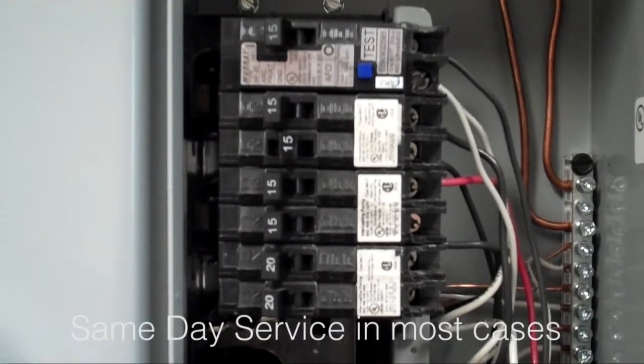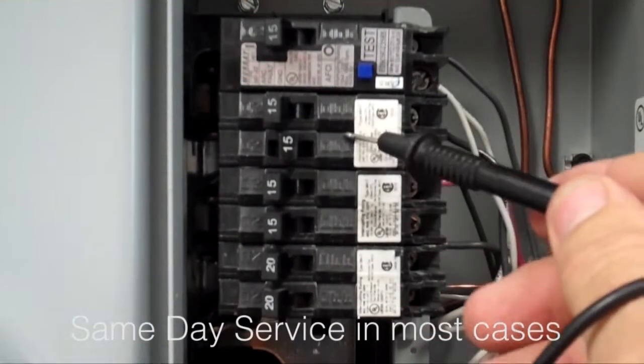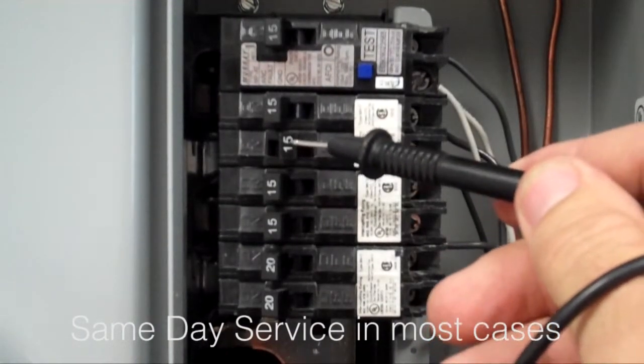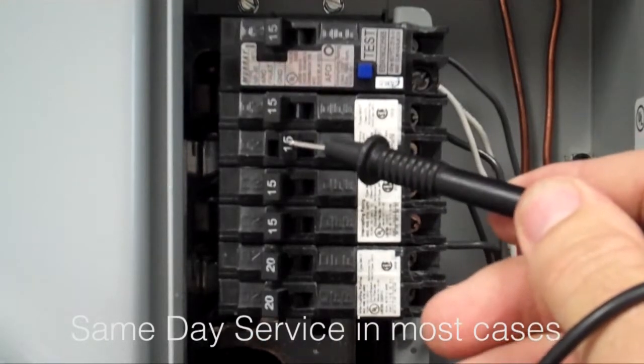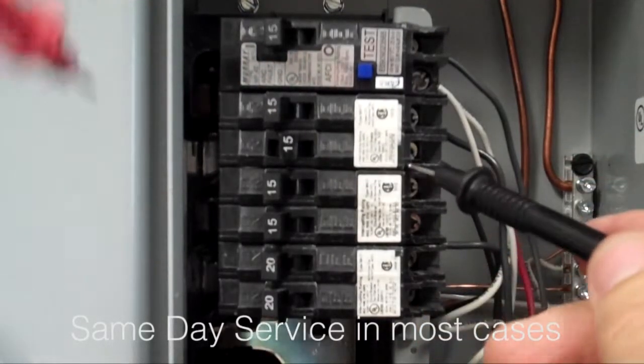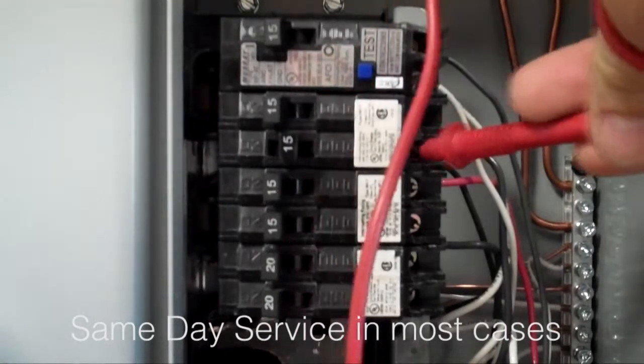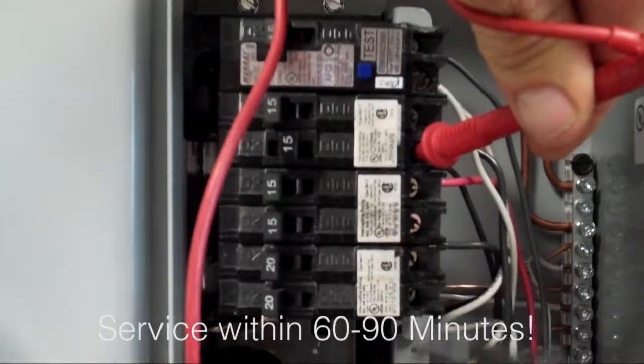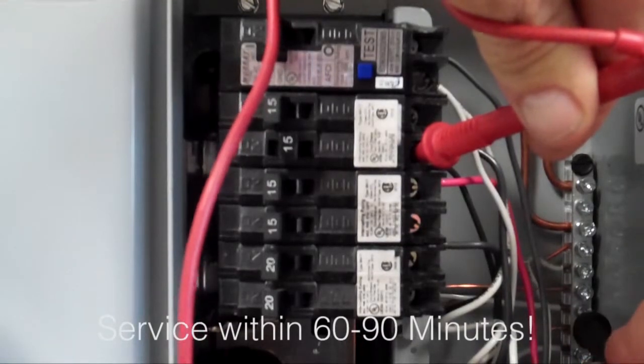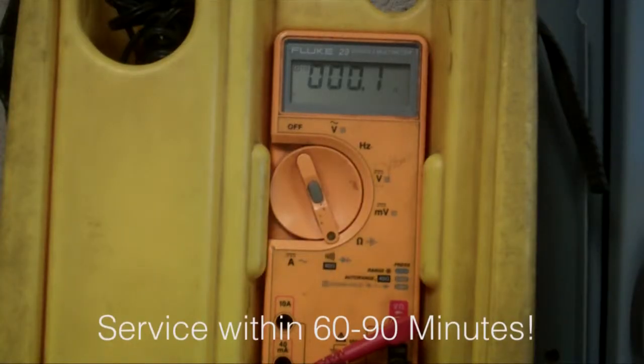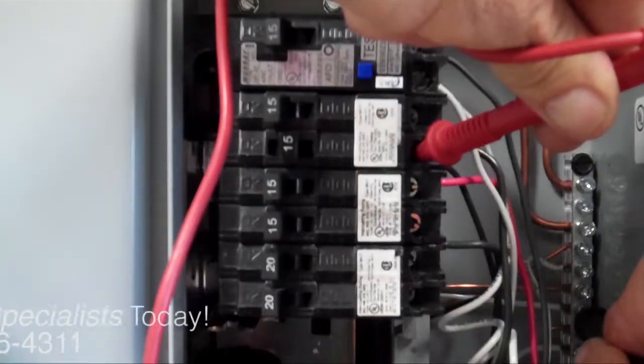Here we are. We see this is the circuit breaker that has tripped. Let's put our test lead on this circuit, then take the other test lead to the neutral and ground bar. We hear that tone coming from the multimeter, and it's picking up 0.1 ohms — that's pretty much a direct short.